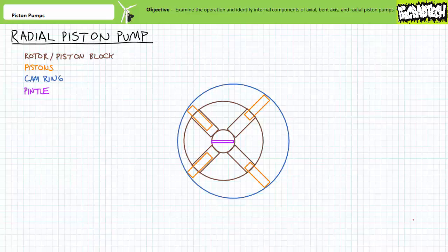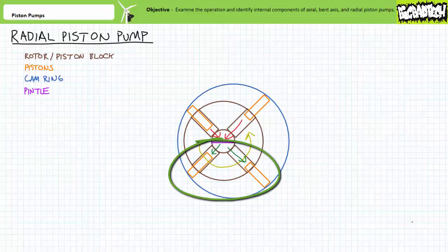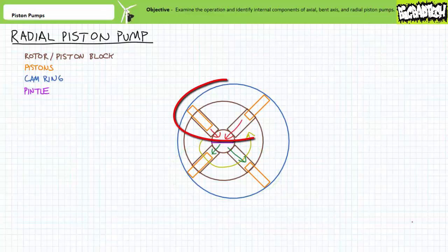Consider a radically different type of piston pump — the radial piston pump. The radial piston pump is what happens when an unbalanced vane pump and an axial piston pump have a baby. Quite like an unbalanced vane pump, it features an off-center rotor inside a cam ring. The vanes have been replaced with pistons, and the rotor is essentially a piston block with pistons that reciprocate radially in and out of it, as opposed to axially. If the rotor-piston block combination rotates counterclockwise, pistons on the lower half would execute the suction phase and pistons on the upper half the compression and exhaust phase.